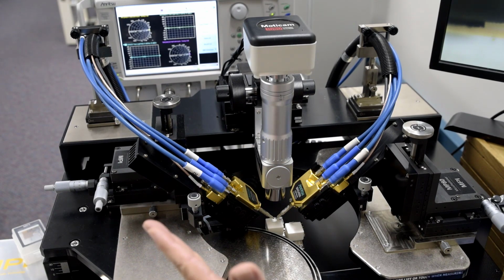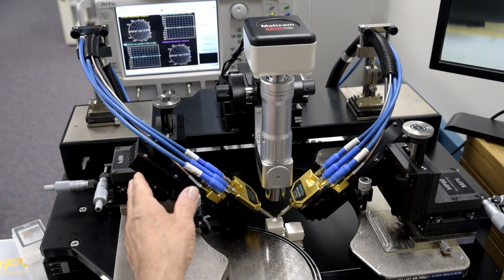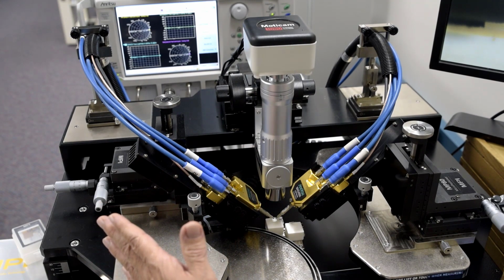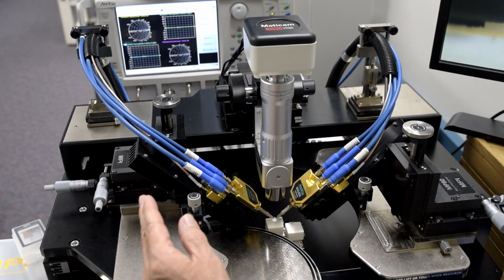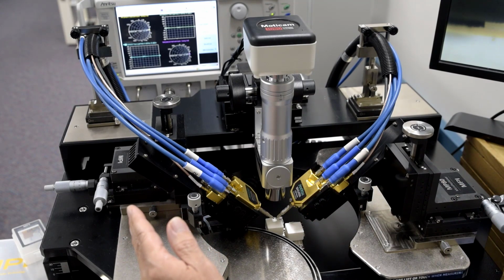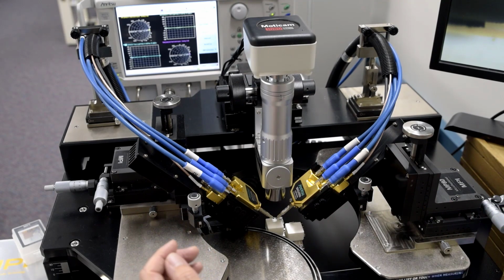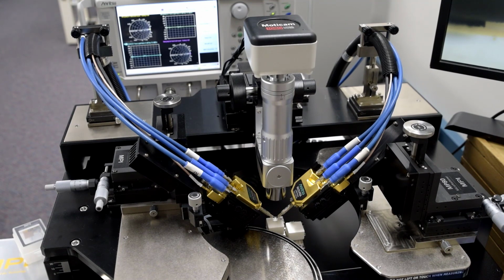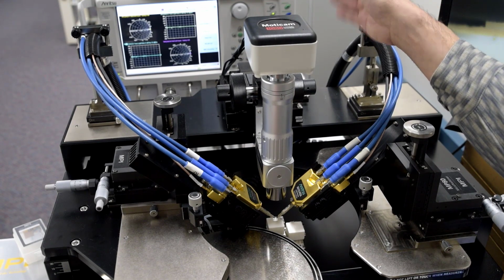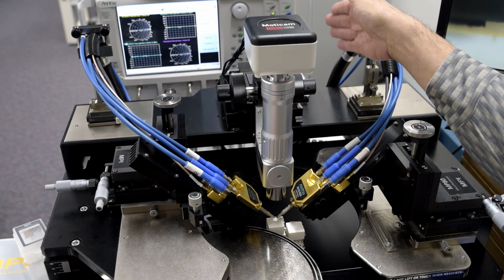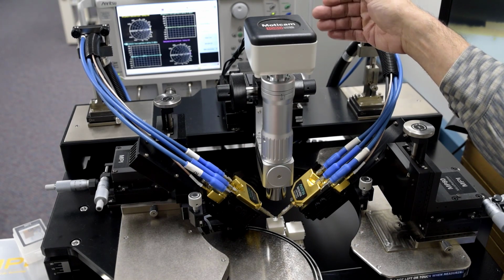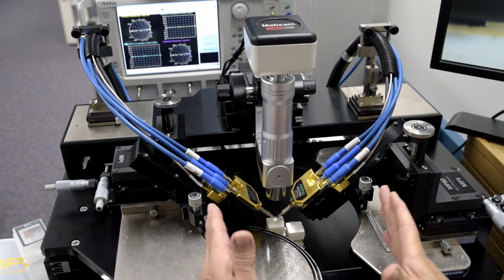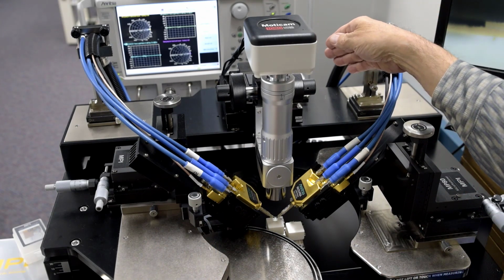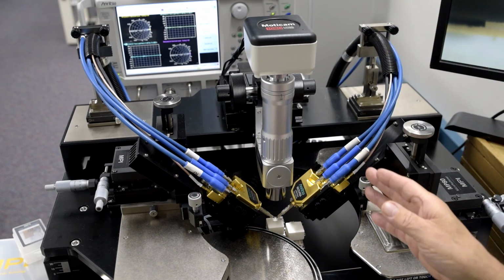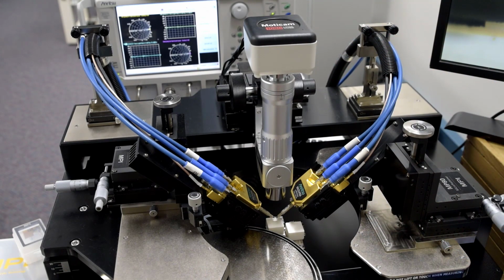However, the added loss will reduce the raw directivity of the system, and any temperature variation or flexing of the cables, if that might happen, will have an impact on your calibration stability. As far as the rest of the system, we have the VNA behind the probe station, elevated so that it is as close as possible to the chuck, and that allows you to shorten the interface cables to as close to a minimum as possible.